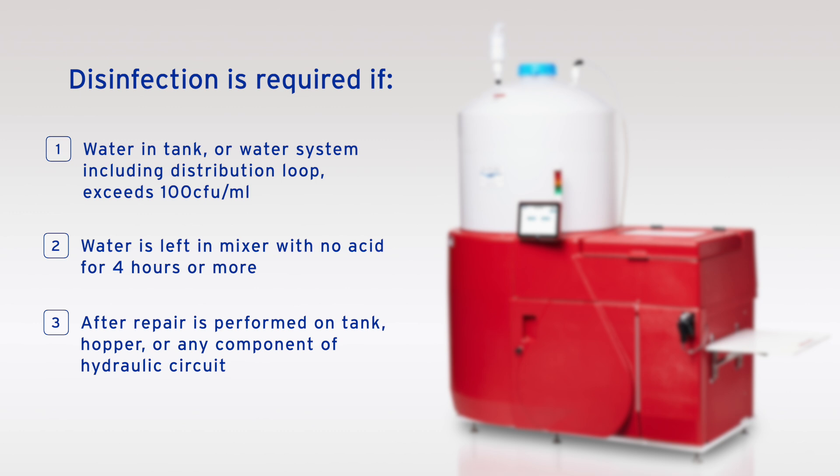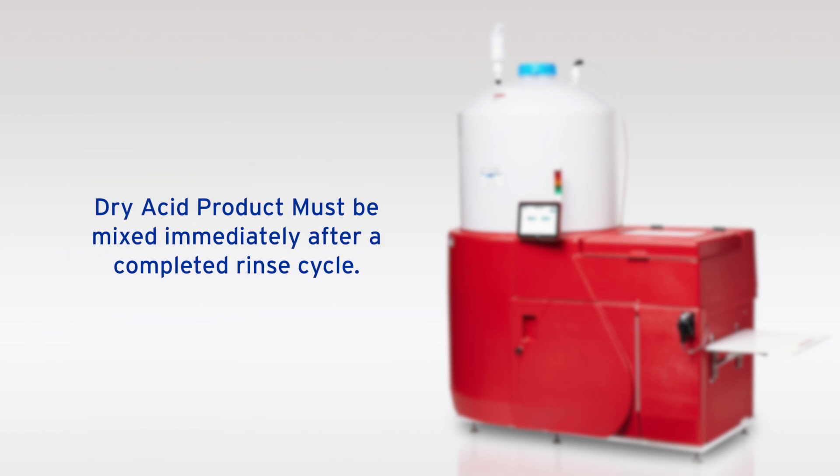3. After repair is performed on tank, hopper, or any component of hydraulic circuit. If water unmixed with dry acid concentrate remains in the Acumix tank for 4 hours or more, Acumix will require the water to be discarded and a disinfection cycle to be completed. Therefore, mix the dry acid product immediately after any rinse cycle.